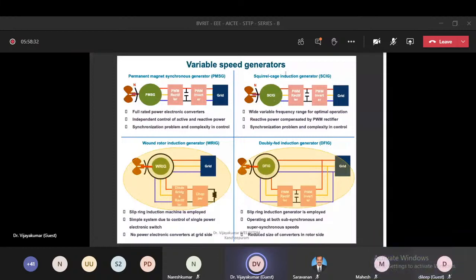Earlier, in the fixed speed wind turbines, there were no power electronic converters. But here, you connect the power electronic converters in between your generator and the grid. These back-to-back converters are bidirectional converters. So the magnetizing current required by this squirrel cage machine is supplied by the rotor side converter because of the bidirectional nature. So once you use the bidirectional converters, you need not connect the capacitors here.